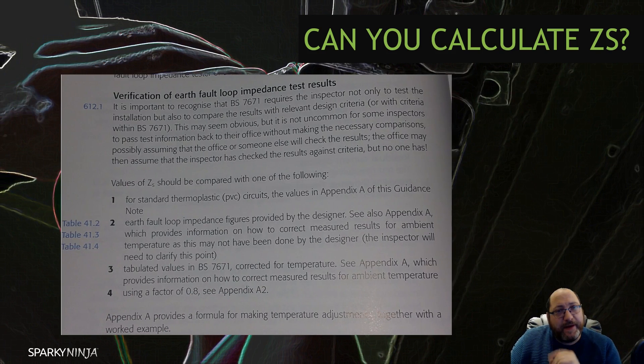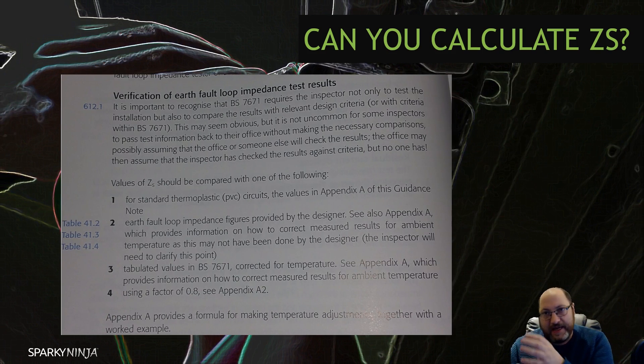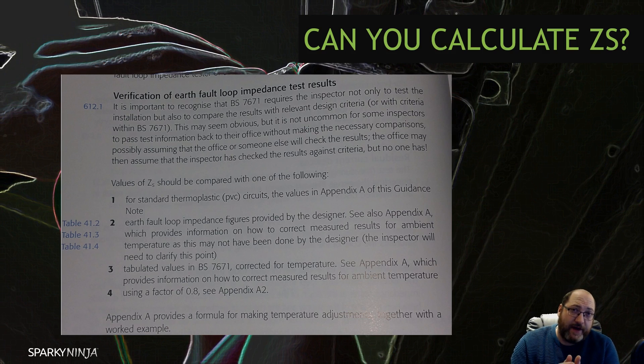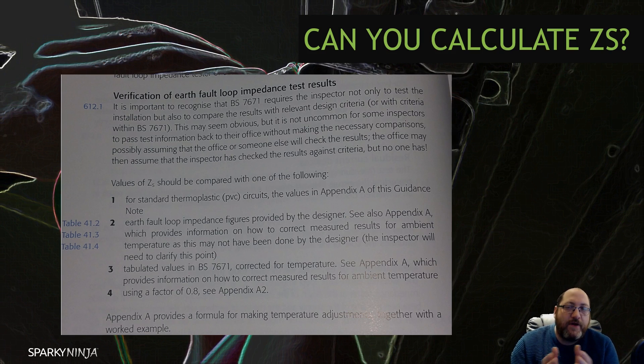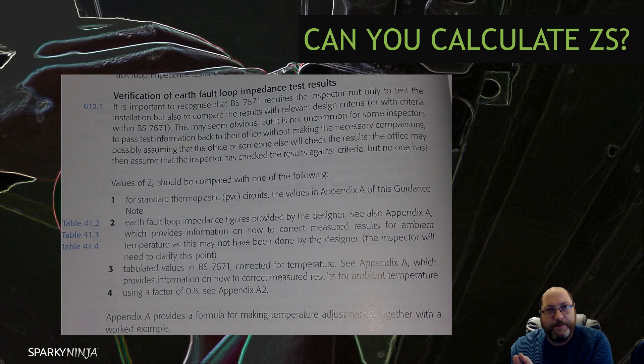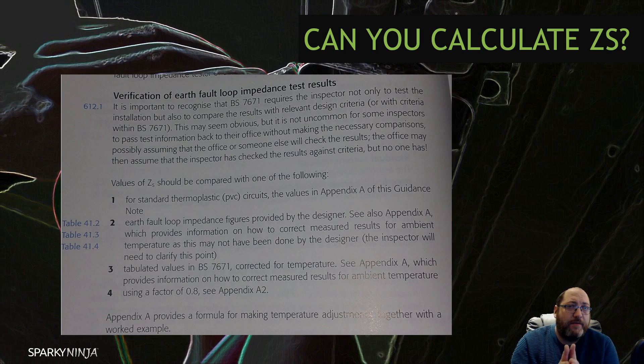After the description of how to test, it does have a bit about verification of the earth fault loop — it's not only the inspector's job to take measurements on site, it's also the inspector's or someone in the office's job to verify the data is correct. Verification of test measurements must be made. And that is where calculation really is used: we use calculation to design and to verify; we use measurement to measure the bit in the middle. Calculation for design, measurement, calculation for verification.